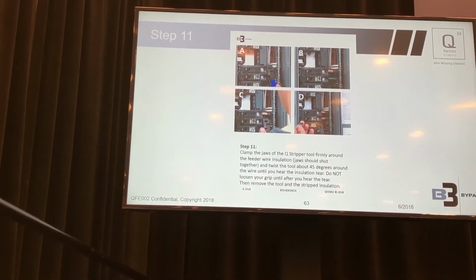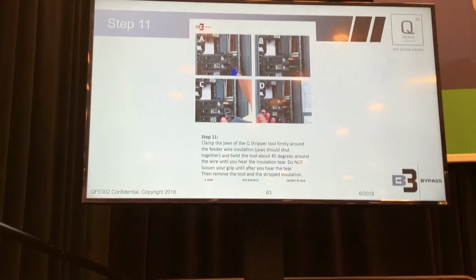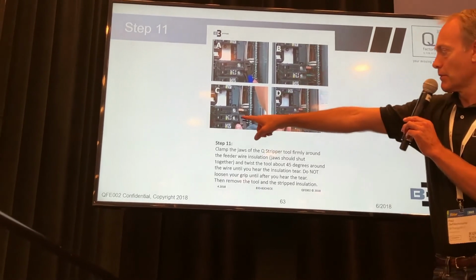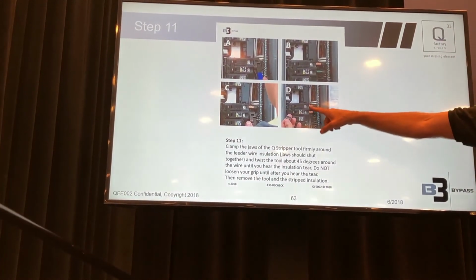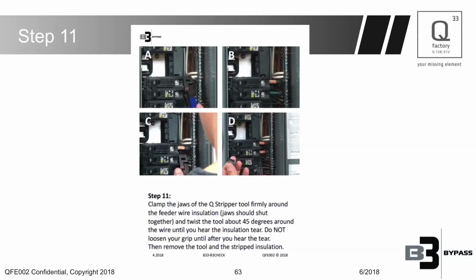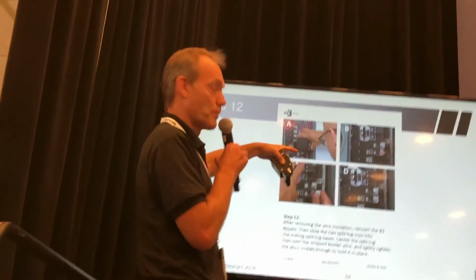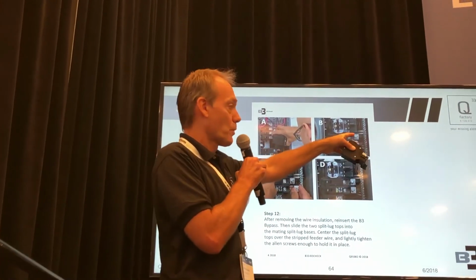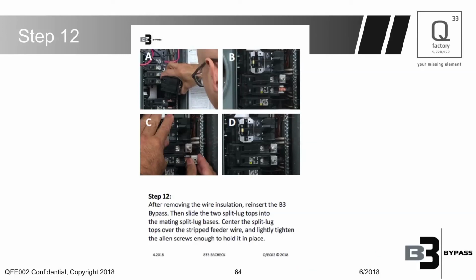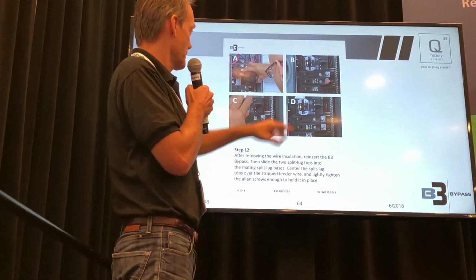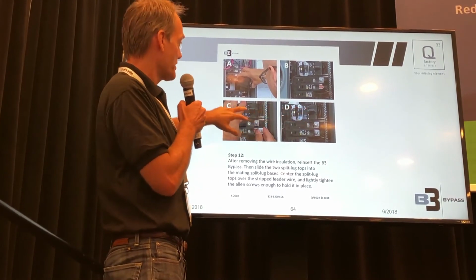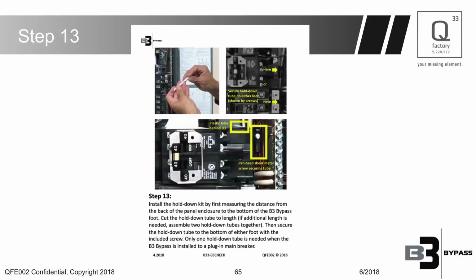After you strip both feeder wires, here we show the top feeder wire stripped. We're stripping the bottom one. Now they're both stripped, so you see the bare copper here. After that is done, you're going to reinstall the B3. We're popping the B3 in right above the main breaker. We're sliding the split lug covers over the split lug bases. Just finger tighten them to keep them in place. Now you have both split lug covers in place. It's a really, really simple installation.